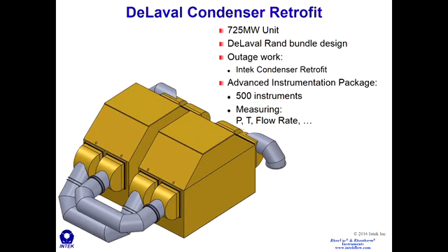This is another unique condenser retrofit. This is the De Laval condenser. This retrofit we performed without any other work to the condenser, so there was no retubing, there was no turbine work. It was just simply our condenser retrofit project. And so we installed several measurements.